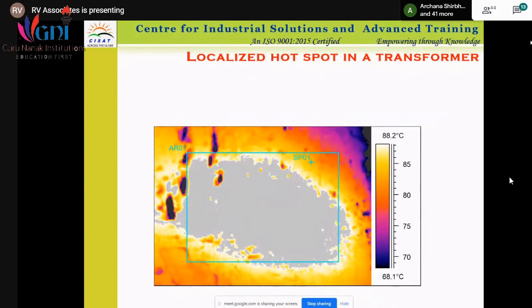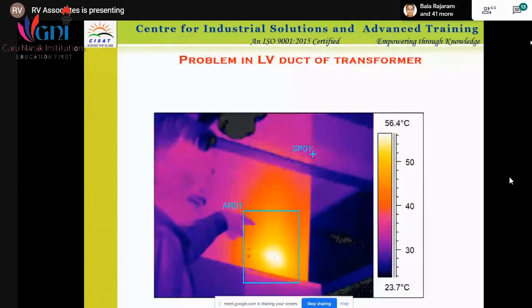Hotspots will be created in the transformer because of unequal distribution of heat. Such hotspots have been shown by thermography. This is the LV duct of the transformer. One of the ducts is getting heated. Okay, this is all complete. How do you see that the system is there? If you don't act on this particular indication, it is like an alarm. If you don't act, then it may lead to a fault in the system. So that's why it has been called a predictive and preventive maintenance technique.